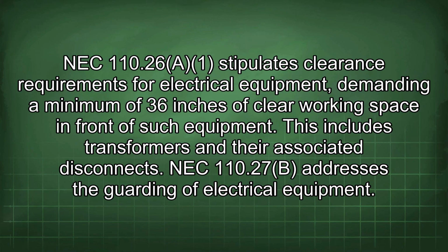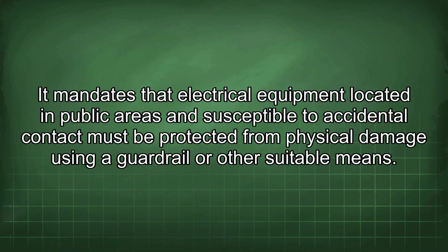NEC 110.26(A)(1) stipulates clearance requirements for electrical equipment, demanding a minimum of 36 inches of clear working space in front of such equipment. This includes transformers and their associated disconnects. NEC 110.27(B) addresses the guarding of electrical equipment. It mandates that electrical equipment located in public areas and susceptible to accidental contact must be protected from physical damage using a guardrail or other suitable means.